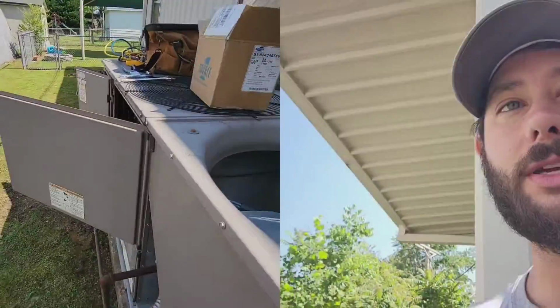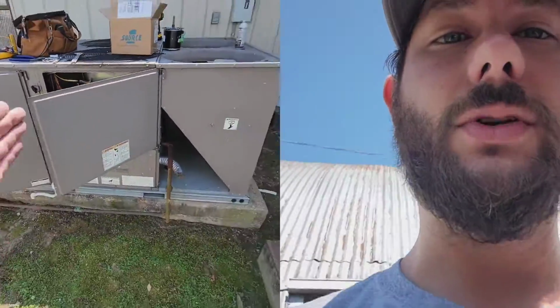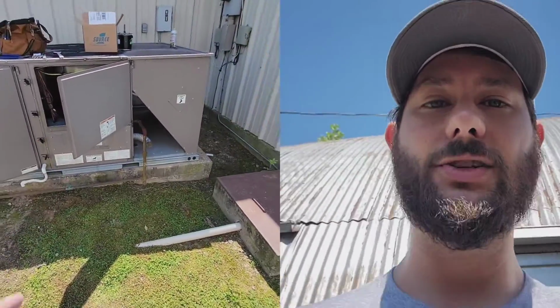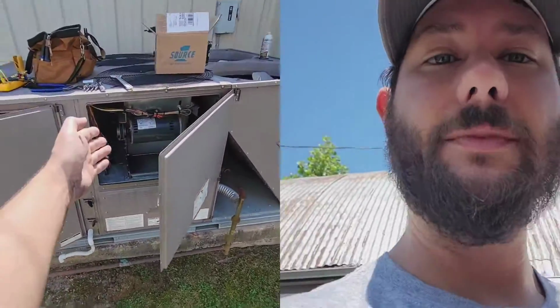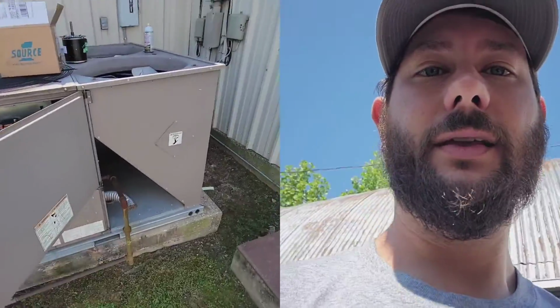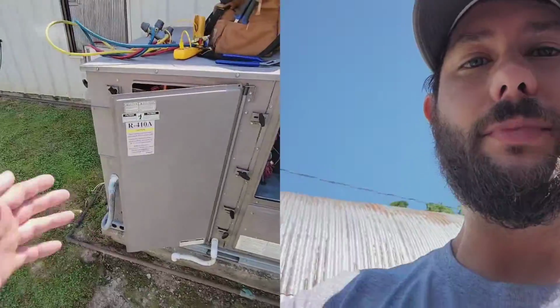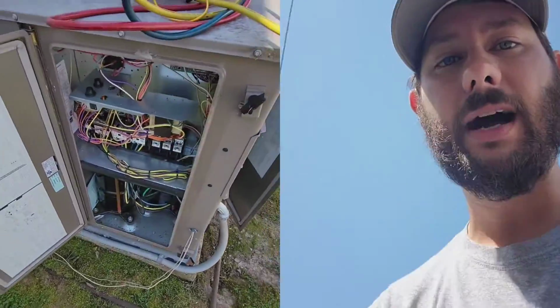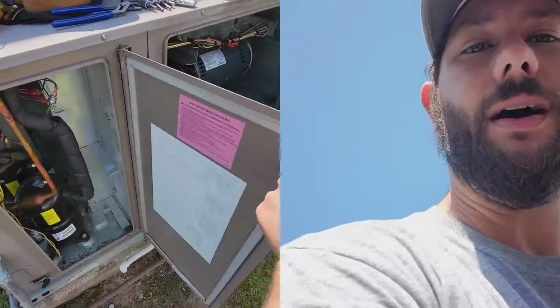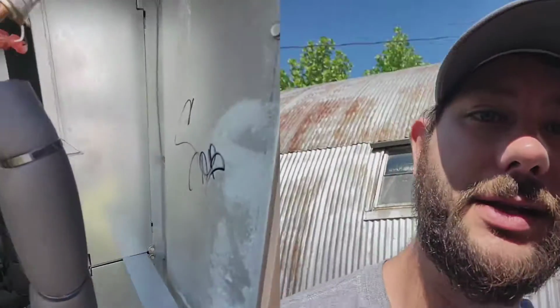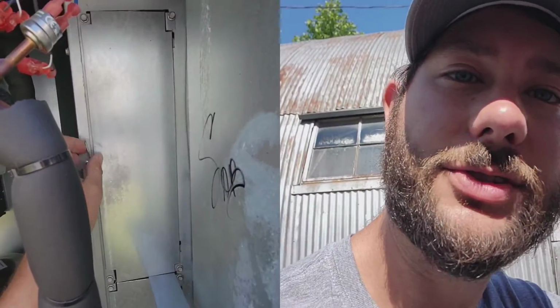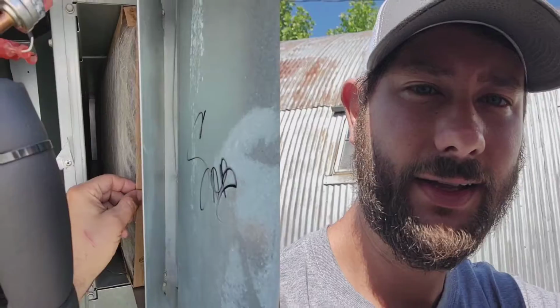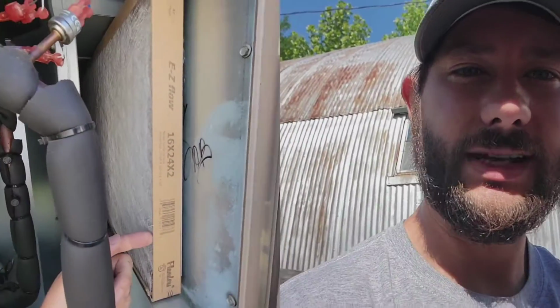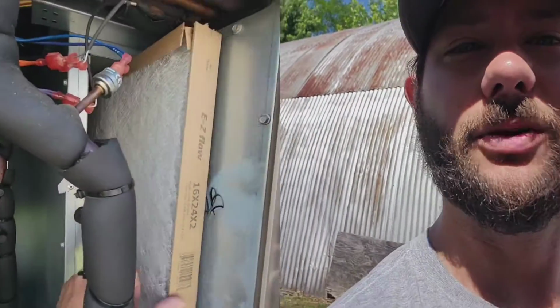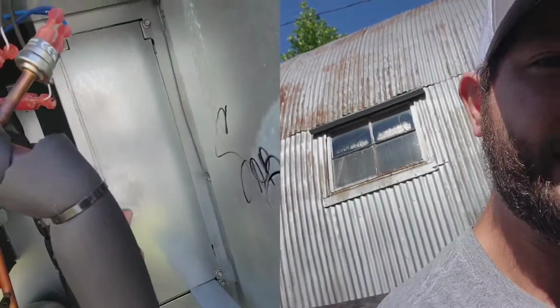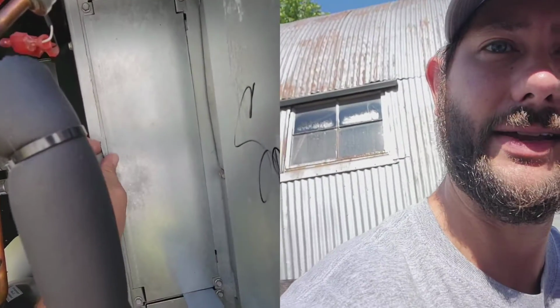Now, normally what you find wrong on commercial rooftop or commercial ground package units is fan belts, dirty coils, bad fan motors, bad electrical components. You could have bad contactors. The most obvious problems are maintenance, and that's why you need to make sure you check your filters. This right here is your filter section. Open that up. Looks like we got two 16 by 24 by 2s, and they're perfectly clean, and that's nice. Nice to see some good maintenance on a unit.